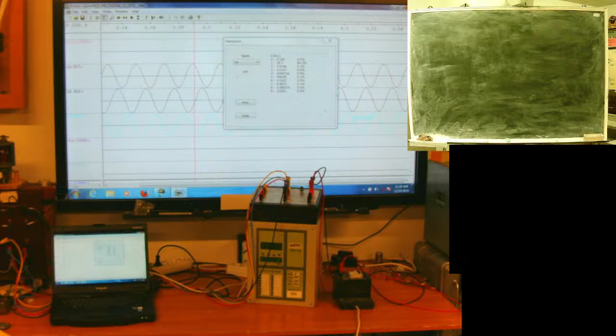Tiny problem. Signal has an offset of 0.4%, and a small presence of second and third harmonic. Mostly this one. Interesting, it has a fifth harmonic. Voltage isn't ideal. Effective takes into account all harmonic components, while on the diagram only the 50 Hz component is taken. That's why you see this difference.